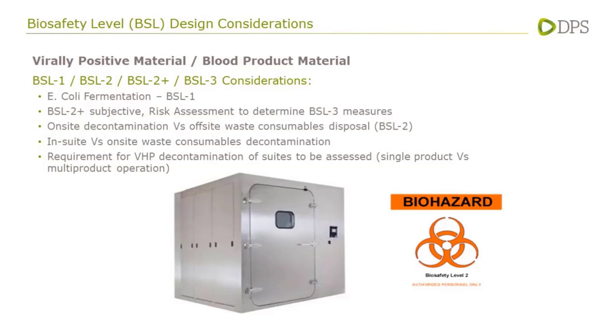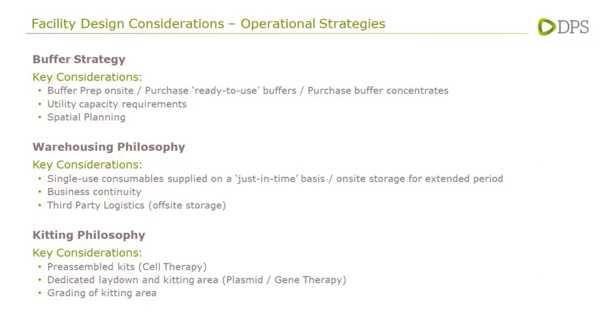Other considerations are operational strategies, which all factor into the facility design with respect to spatial constraints, utility requirements, and how the facility is planned out. The first is the buffer strategy: different approaches depending on scale include making buffers on site, purchasing ready-to-use buffers, or purchasing concentrates and diluting them in-line into the process. These different strategies speak to different requirements with respect to onsite buffer prep capacity, utility capacity, and staging requirements.